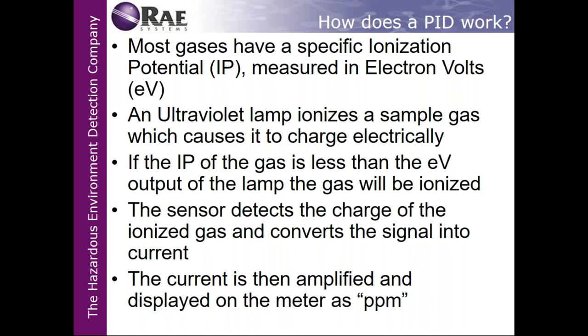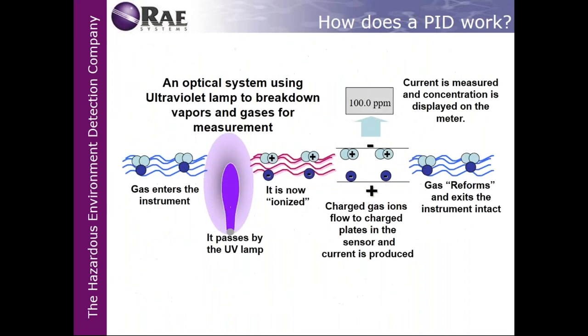Most gases have a specific ionization potential, or an IP, measured in electron volts. An ultraviolet lamp ionizes a sample gas, which causes it to electronically charge. If the IP of the gas is less than the electron volts of the output of the lamp, it will be ionized. If it's higher than the eV the lamp is rated for, it's just going to pass on through, so it will not ionize. The sensor detects the charge of the ionized gas and converts the signal into a current. The current then is amplified and displayed on the meter in ppm or in parts per billion.